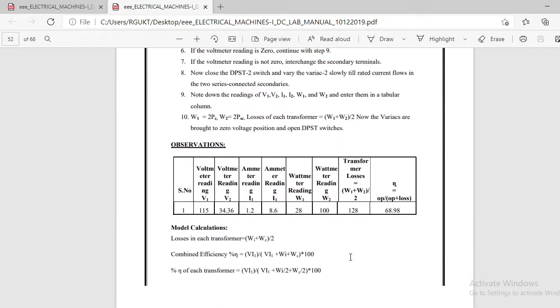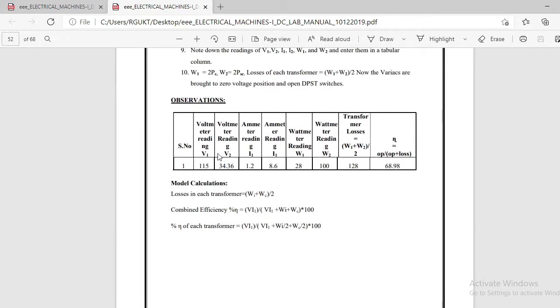So what is the observation table related to this experiment? This is the voltmeter reading under no load, 115 volts we need to apply, and the voltmeter reading on short circuit. The rated current here is 8.6 amperes. For this 8.6 amperes, the meter reading is 1.2 under no load. Next, the wattmeter readings: iron losses are 28, copper losses are 100. So combined it is 28 plus 100, 128, and for each transformer it is divided by 2.